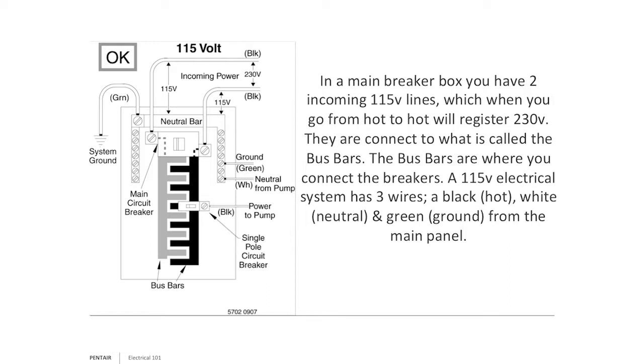When troubleshooting pumps, I don't care what you measure to ground. I don't care if you measure L1 to ground or L2 to ground. It's measuring across L1 and L2 — across the pump or T1/T2 on a control like a pressure switch — that matters. We have two 115-volt lines coming in that, if measured across properly, measure 230 volts. Those 115 lines go to bus bars — a gray bus bar and a black bus bar. Think of it like a two-cylinder engine with the cylinders firing opposite each other. From there, a single-pole single-throw breaker sends a black line out to your outlet.